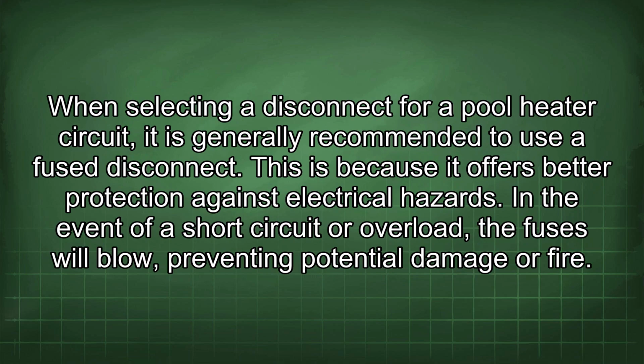When selecting a disconnect for a pool heater circuit, it is generally recommended to use a fused disconnect. This is because it offers better protection against electrical hazards. In the event of a short circuit or overload, the fuses will blow, preventing potential damage or fire.